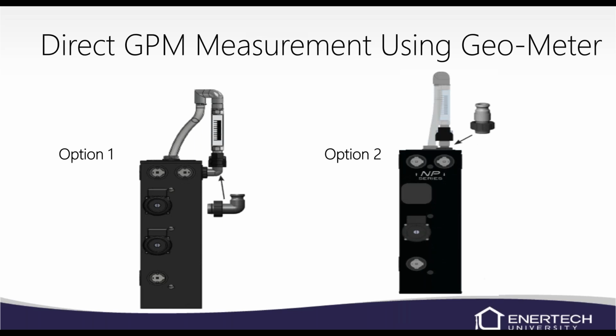You can also install option 2, where you can leave it in the circuit, but I would never recommend leaving it in the circuit. You guys have probably seen boilers, sight glasses, and other sight glasses. Usually after about a year or so, you're not going to be able to read it. So it's best just to set it once. It's not going to change unless you lose a pump. So once you set it, you shouldn't have to really worry too much about the flow changing any.